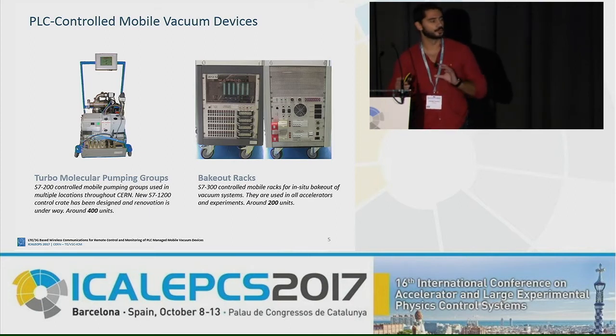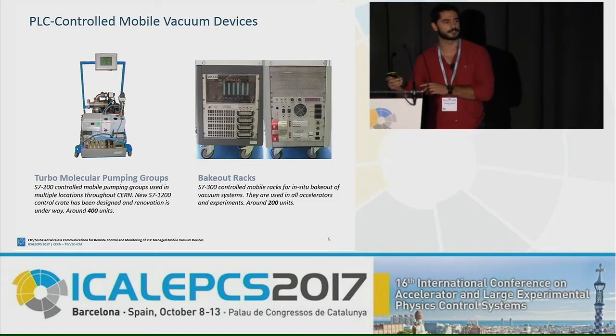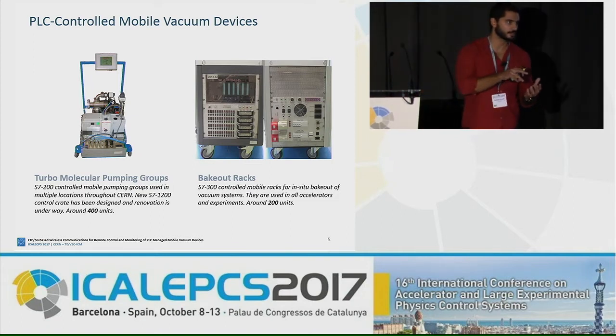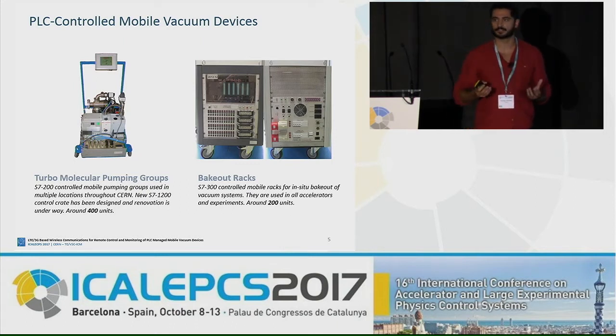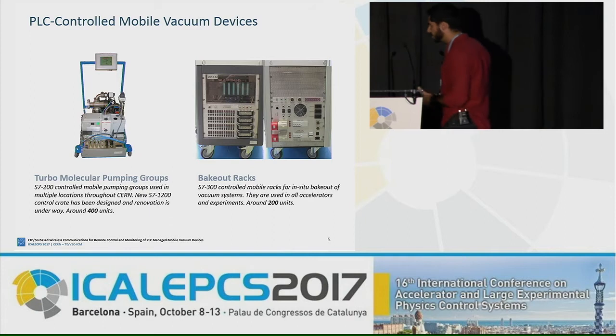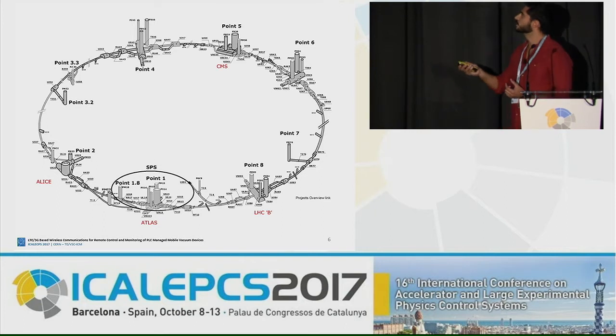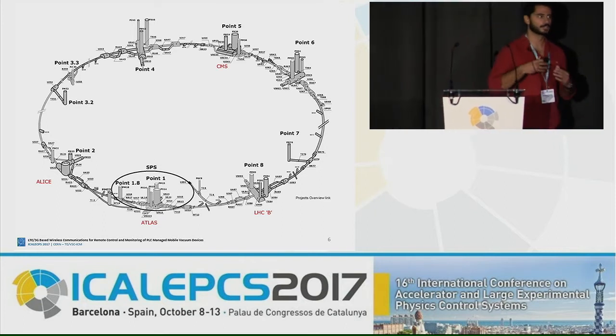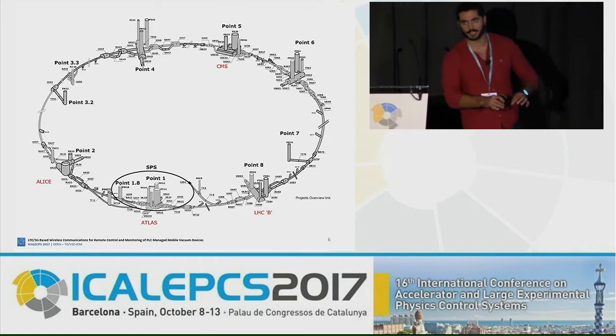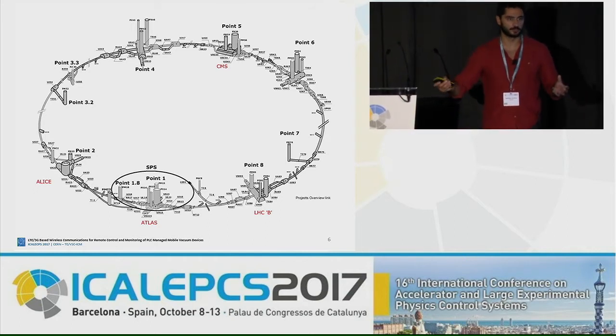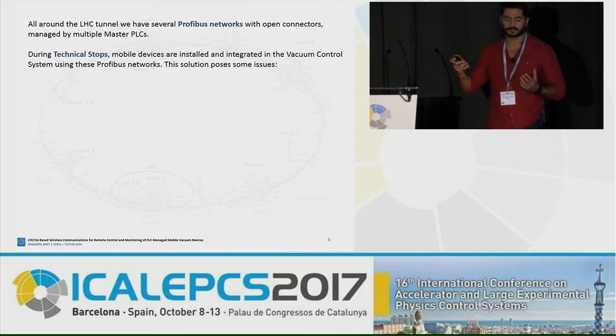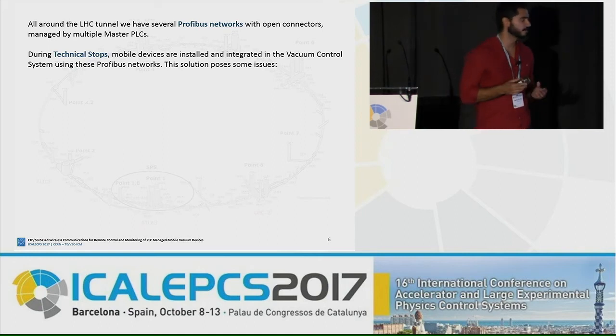This happens during technical stops, and only during technical stops, because they cannot be in the tunnel during operation due to radiation. During these technical stops, the operators move these two devices next to the tunnels and, using their touch panel, specify their location. For the pumping groups, it's the flange they connect it to. For the bakeout racks, it's the sector they connected it in. And obviously, if we have them working, we want to integrate them in our control system. Right now, this is done using Profibus. All around the LHC, we have several Profibus networks with several masters. These cables have open connectors to which the operator connects our mobile device. So during technical stops, these devices are installed and integrated into our vacuum control system.